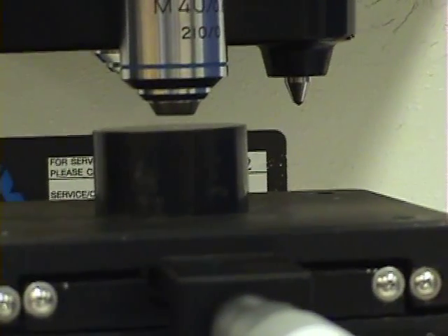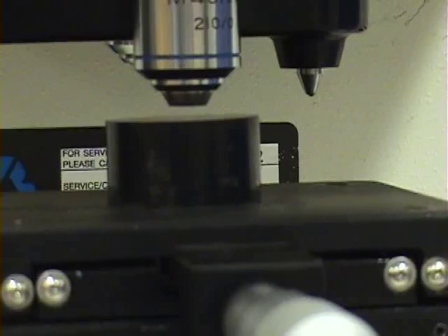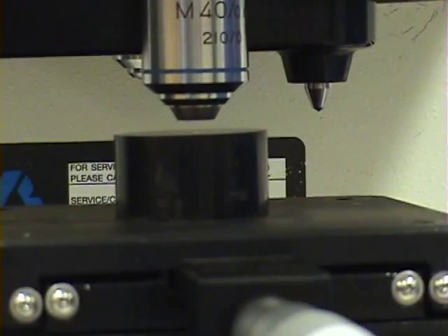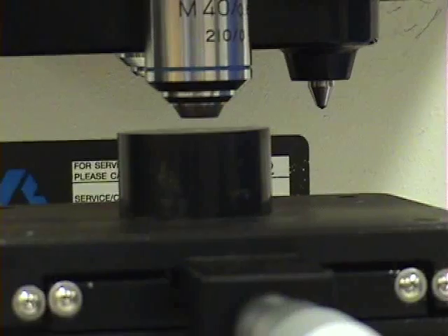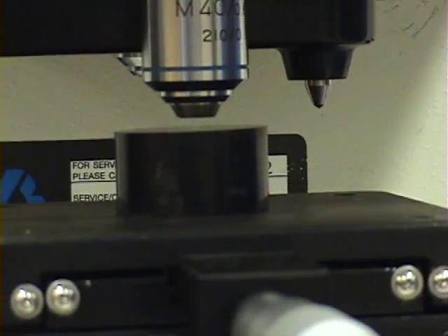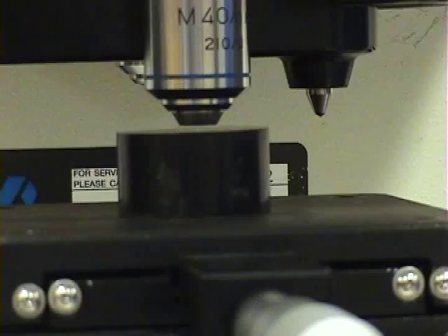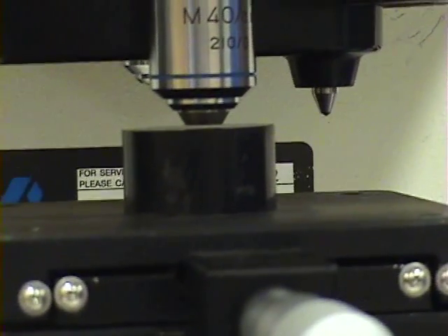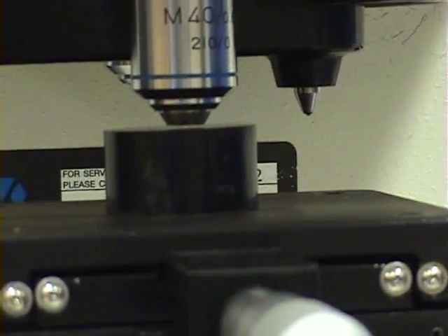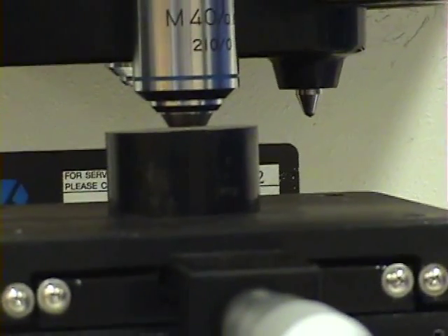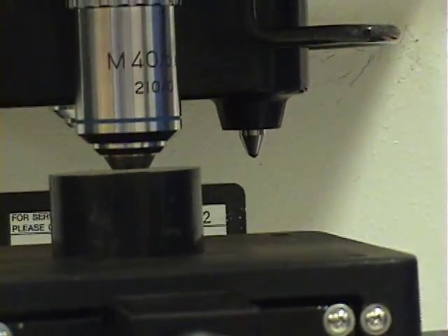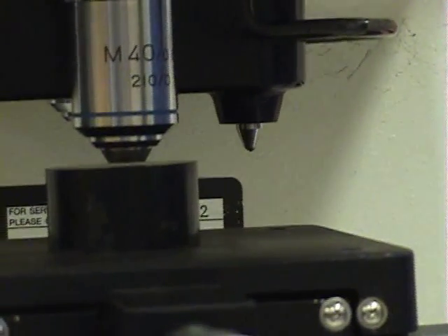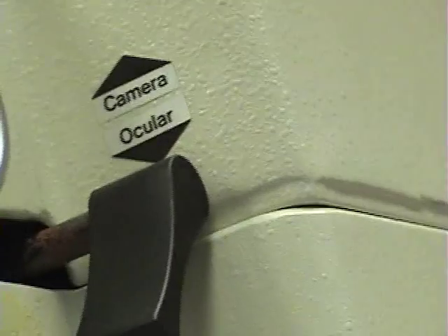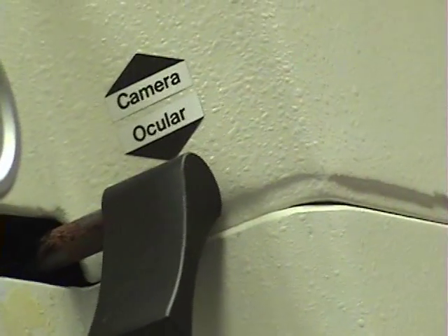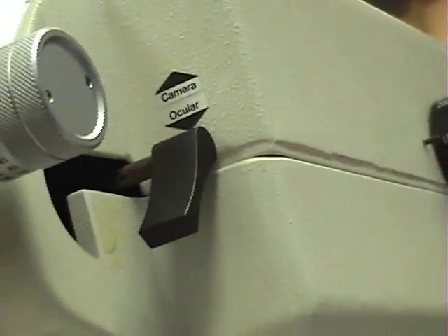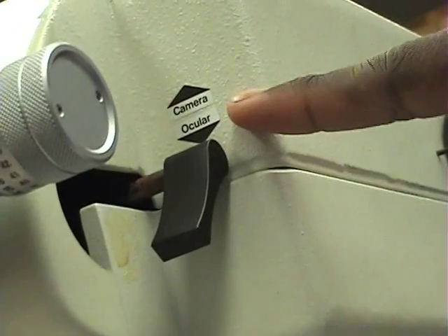Now that we have the sample placed up underneath the lens, we're going to move the platform about the Z-axis so it gets closest to the lens without touching the sample, like so. And that right there, ladies and gentlemen, that is perfect. You should also be able to see a small space between the lens and the sample. After you get everything centered with the lens and the sample, make sure that the switch is switched to ocular.